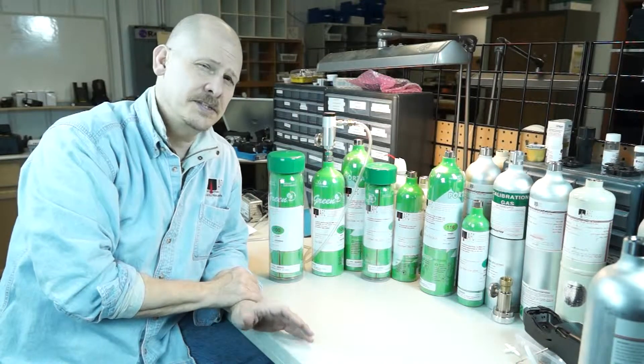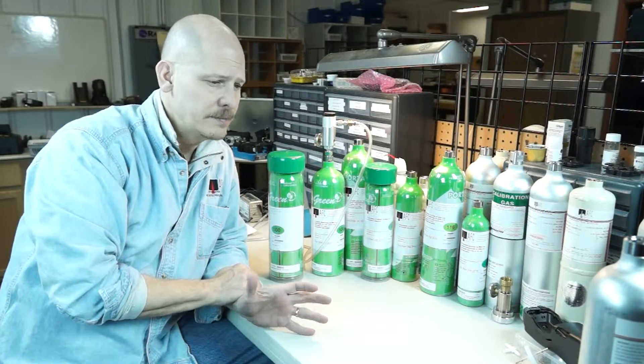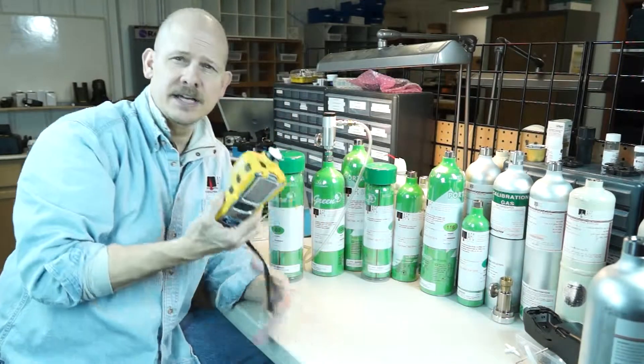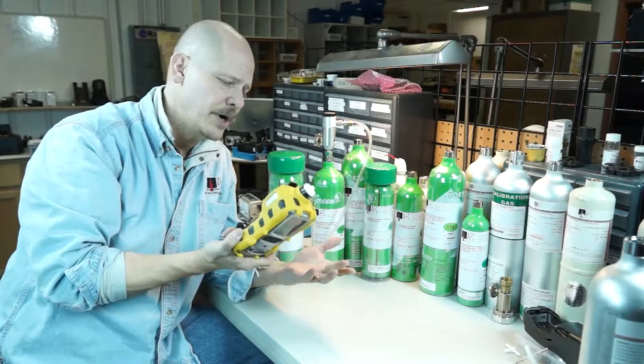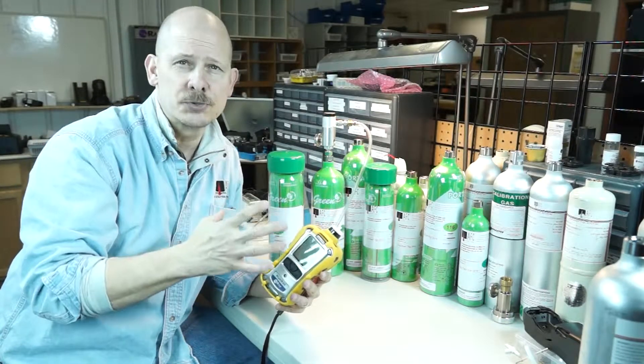The main reason we use Port-A-Gas is the very accurate, precise mixtures that they put together for us. When you're dealing with calibrating gas detection instrumentation of any type, here's a RAE Systems MultiRAE, it's very critical that we make sure we test those sensors periodically.